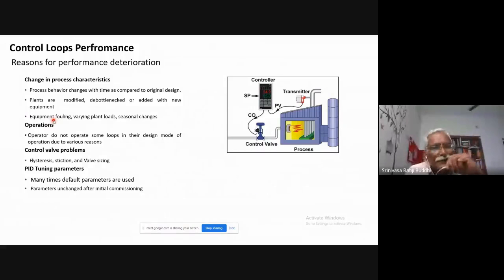All the heat exchangers initially will be good, but gradually they will be fouling. Then you may do the cleaning. During this process of fouling, which takes place continuously, the performance also deteriorates. Then plant loads also will change because, based on the market requirements, you will either increase or decrease the production. That again will have a bearing on the behavior of the process plant, because we know that most chemical processes are non-linear in nature. So if you are operating at different loads, the behavior also will be different.